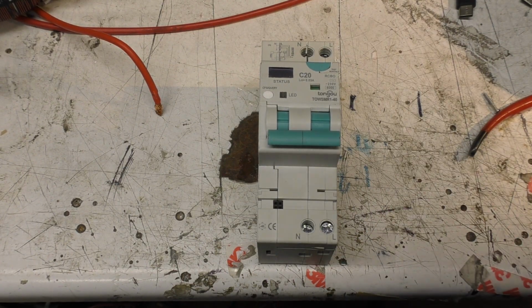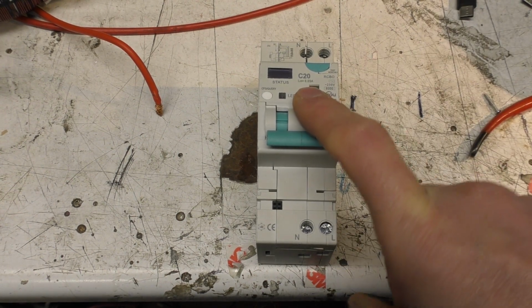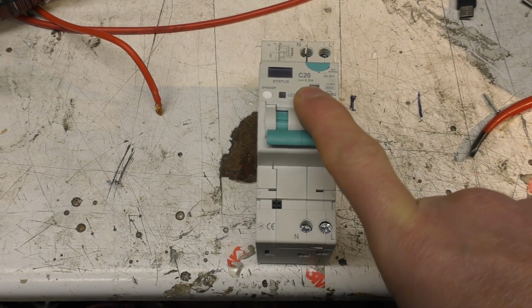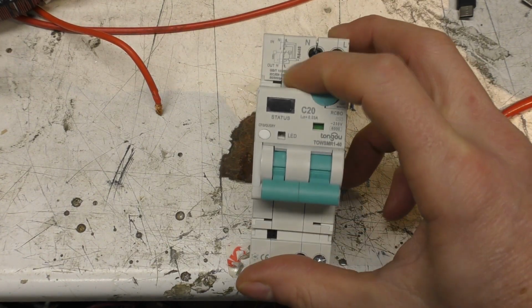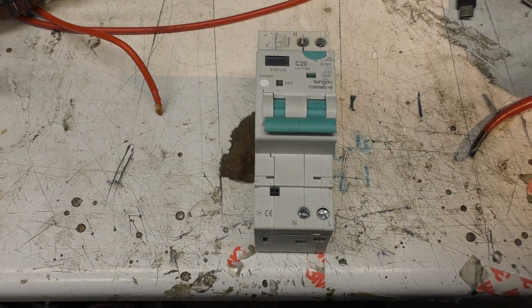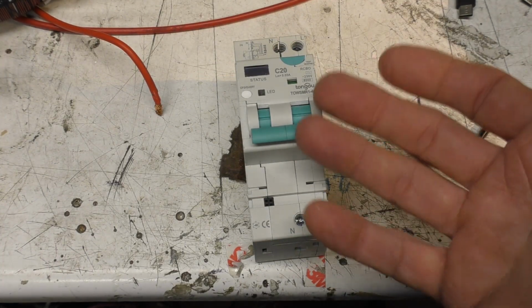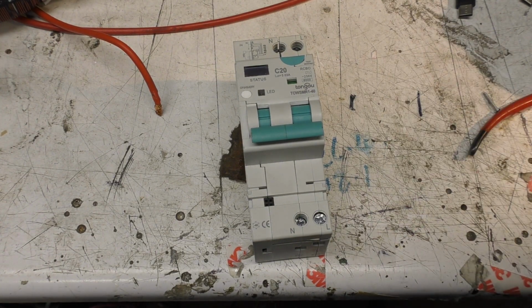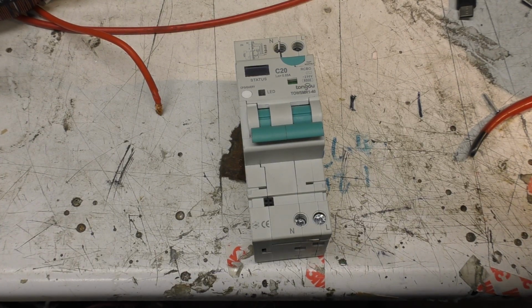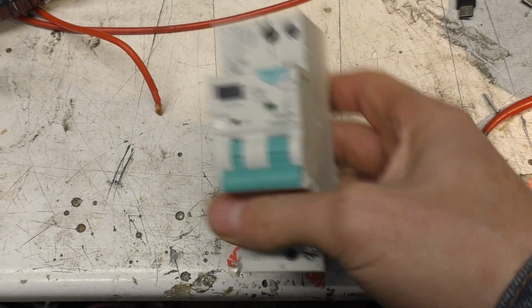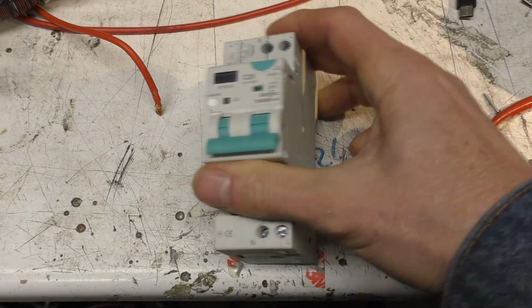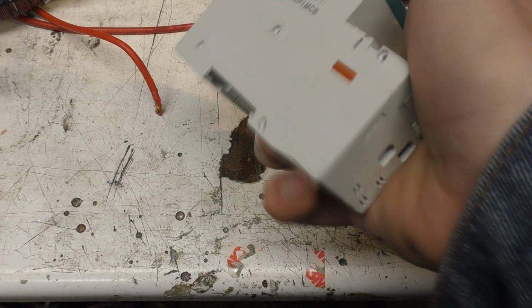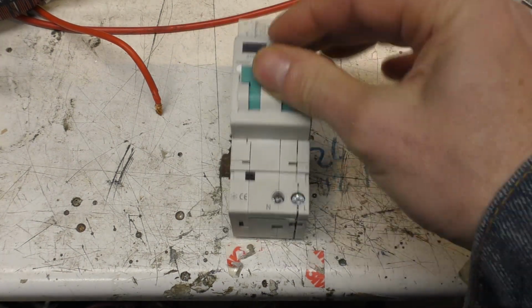Firstly, you've got a device that looks like a circuit breaker, which claims it's got a 30 milliamp earth leakage detection, but that can be disabled and overridden, so it may or may not have it, and therefore can't possibly comply with the IEC specs that it's claiming to. And secondly, the fact that this can be remotely switched on from either a timed event, remote access, or after recovering from an over or under voltage situation means that something in this form factor that does that is just downright dangerous. There will be people that don't realise the dangers of that and install these in place of, as an upgrade to, a standard circuit breaker, and it's a really, really bad idea.